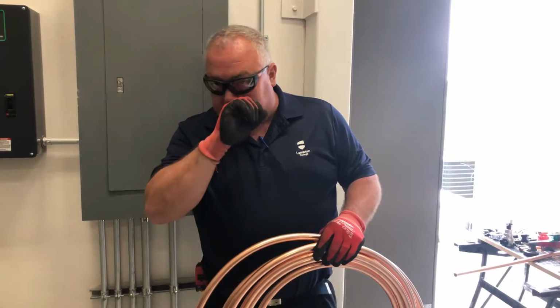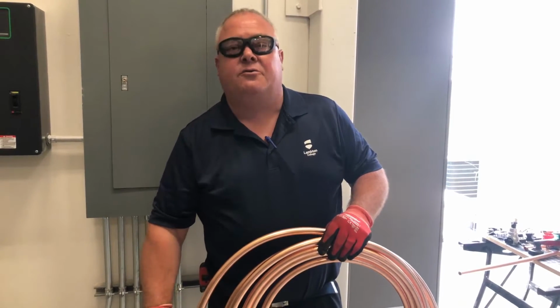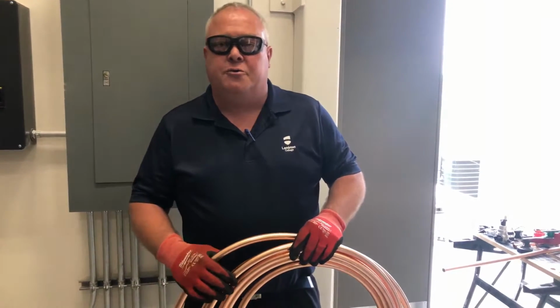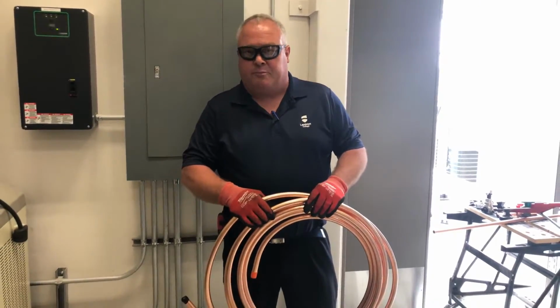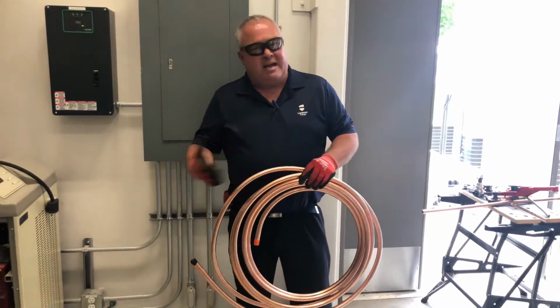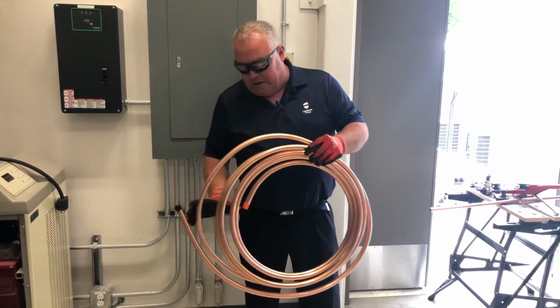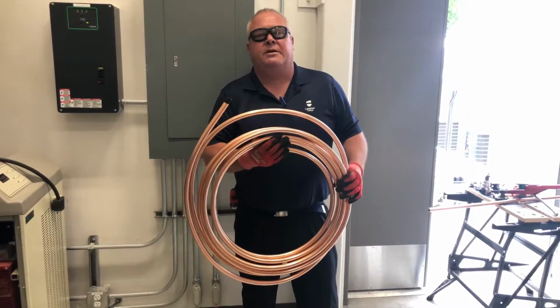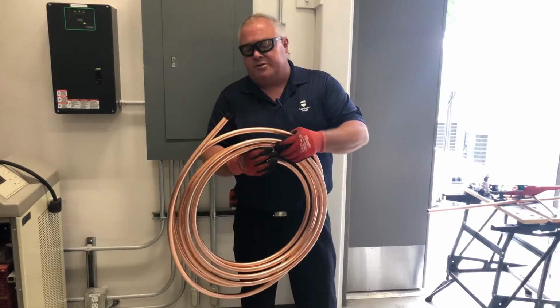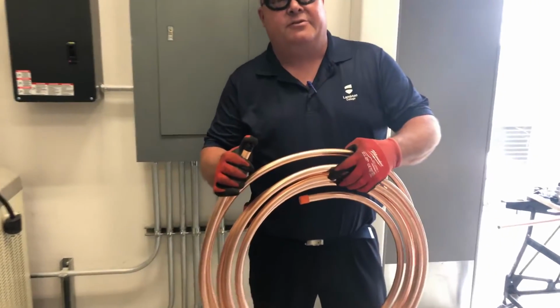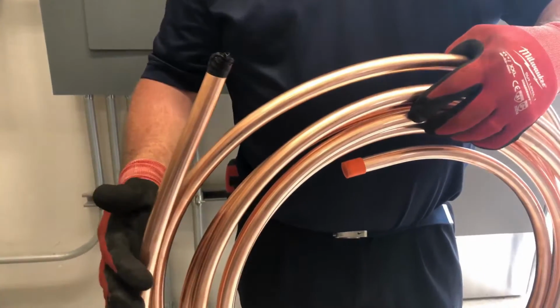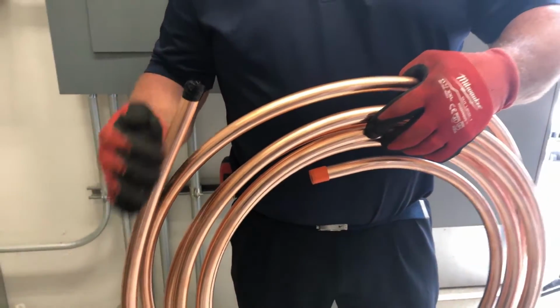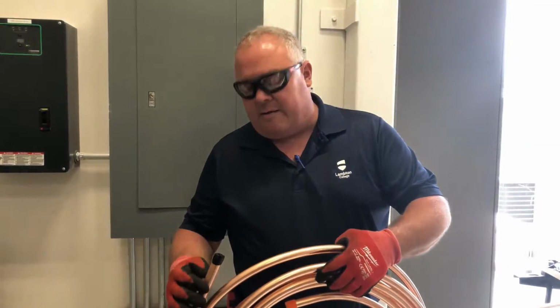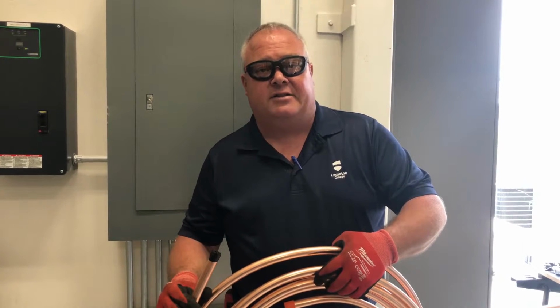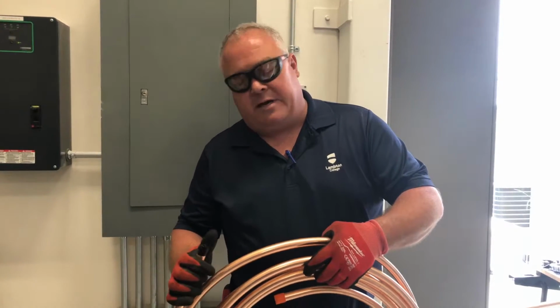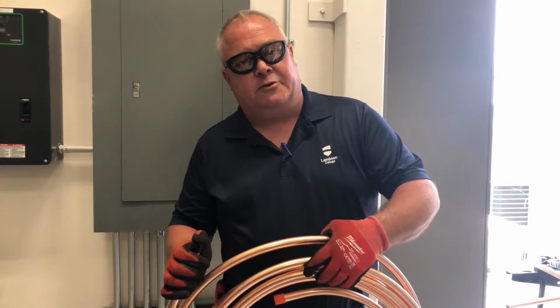One of the applications I want to go through is unrolling some copper tubing, then showing bending and brazing applications, real common things we do in the field. Soft copper tubing, which we normally use, comes in a roll. You'll notice caps or tape on the ends — that's to make sure no dust, debris, or contaminants get inside the tubing. Once we cut the tubing, it's important to cap it up.